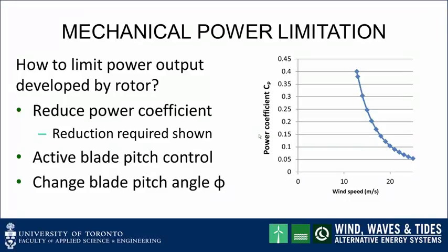How do you limit the power output developed by the rotor? The basic idea is to reduce the power coefficient. The reduction required is shown for a rotor with CP equal to 0.4 at the rated speed of 12.9 meters per second — the rotor behaves normally up to that point, and then we reduce CP to achieve the same rated output at higher wind speeds, essentially making the wind turbine performance degrade. This can be done with active blade pitch control — a mechanism that changes the blade pitch angle φ — as discussed in the lecture on aerodynamic lift techniques.